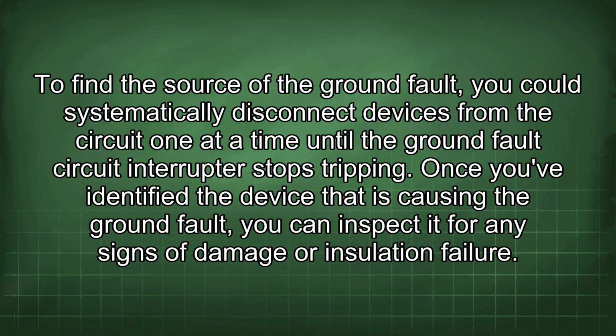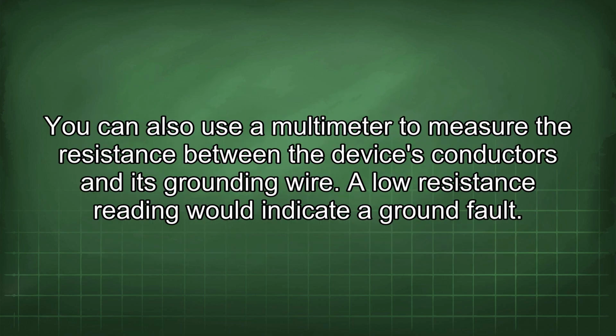Once you've identified the device that is causing the ground fault, you can inspect it for any signs of damage or insulation failure. You can also use a multimeter to measure the resistance between the device's conductors and its grounding wire. A low resistance reading would indicate a ground fault.